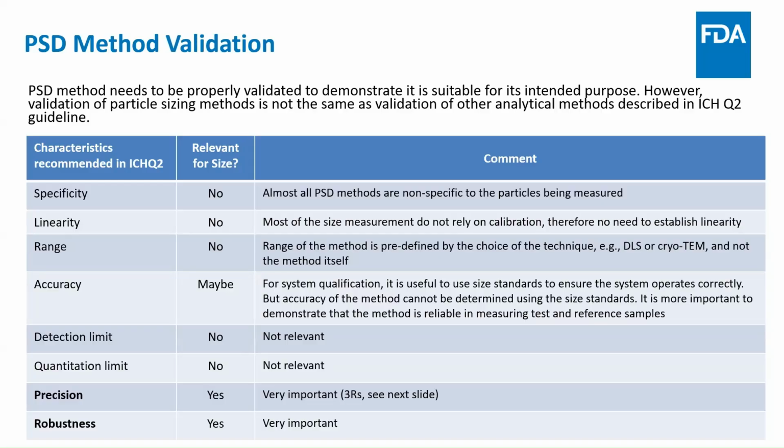What you consider as the value you can trust or not for the sample really depends on the settings, the procedures, the sample preparation procedure for preparing the material of the actual sample, and putting the input of information into the software to perform that sample measurement. What the applicant did for the standard has nothing to do with the accuracy of the measurement of the actual sample. For that reason, this is a really challenging part of the validation, I know.